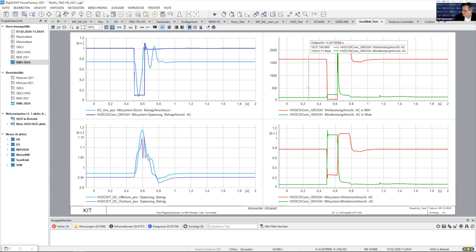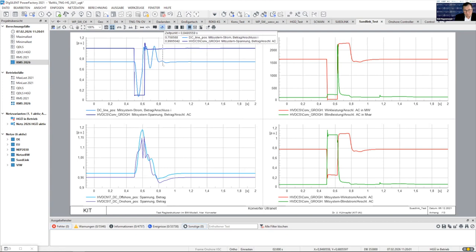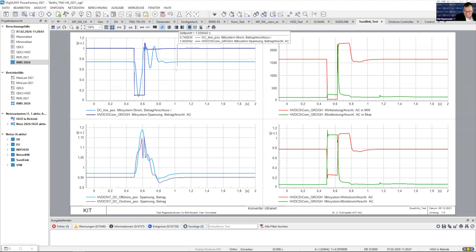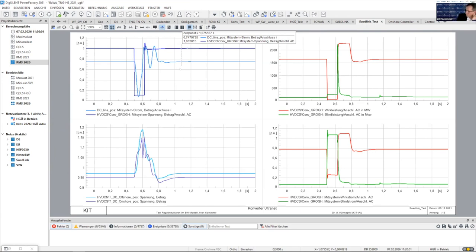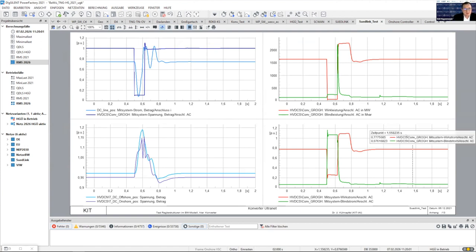Here we set a grid point, set a short circuit on that bus bar, and continue the simulation. We see the short circuit event. By definition a converter must withstand a short circuit for 125 milliseconds. Without any measures, the inverter would pump two gigawatts onto the short circuit — causing sudden overheating and burning of all infrastructure. So we inject reactive power — current is injected at 90 degrees to the voltage — only reactive power, not active power. This is called fault ride-through. The modeled system is doing exactly what is required, shown nicely in the current, voltage, and DC line diagrams. These simulations cover everything from small microgrids to European grids, with time frames from one day to several weeks or down to the sub-second level for electromechanical simulations with one iteration step per millisecond, and data transfer between sites at two kilohertz.